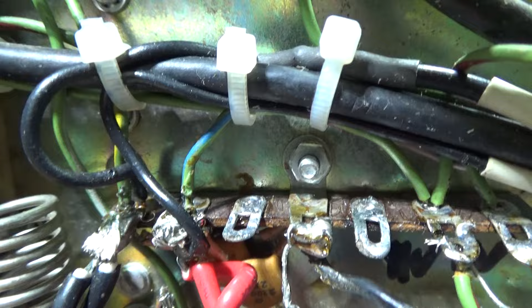Wire number 4, on the negative side of these high voltage diodes, that's the ground. Right here, ground wire, goes over to this ground terminal strip, a grounded terminal strip. That was wire number 4, ground.